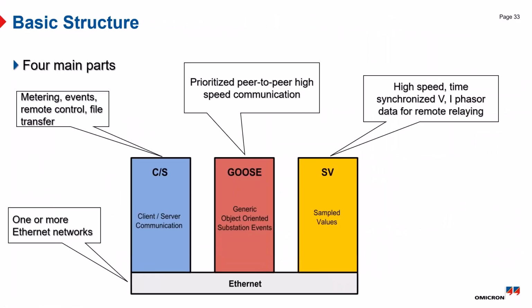So how does this 61850 thing work? If you don't really remember much else, it has 4 different parts. It has a client server part, a GOOSE part, a sample value part, and then a network part. And there are three different services. So GOOSE message, obviously you can read it there, Generic Object Oriented Substation Event. It's actually a digital version of those binary inputs and outputs, those hardwired breaker positions or trip and close commands, whatever we used to have going around in copper in a substation. Now they're going by GOOSE command, and that's real time, it's high speed.